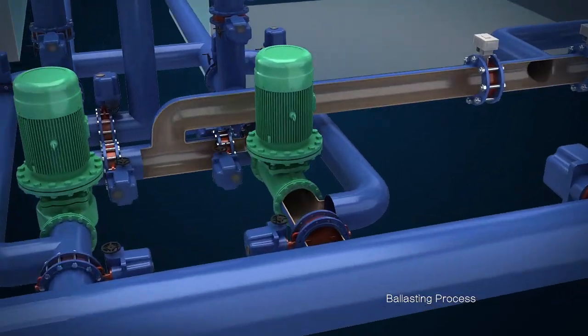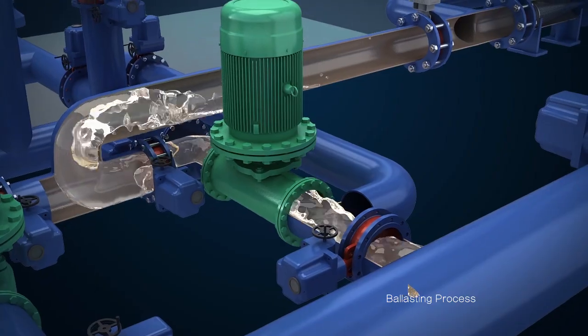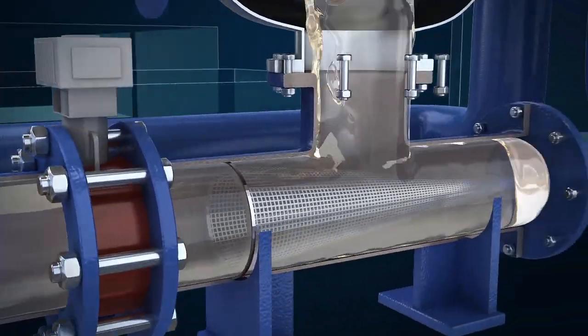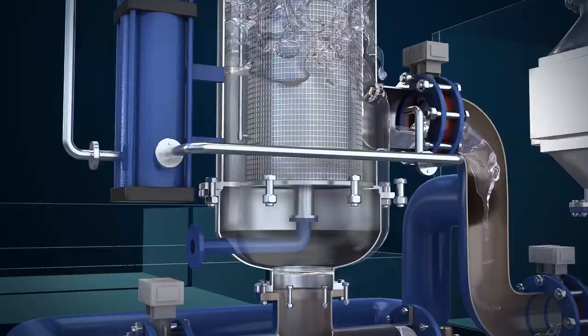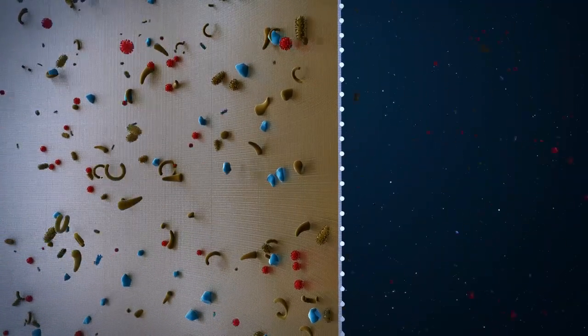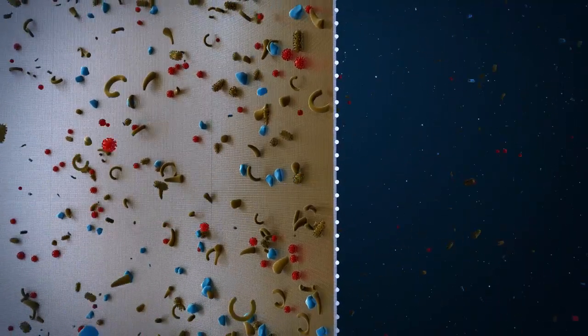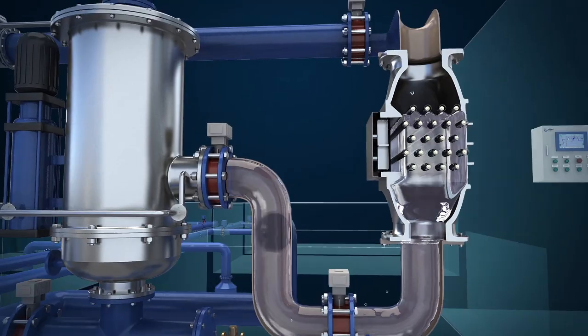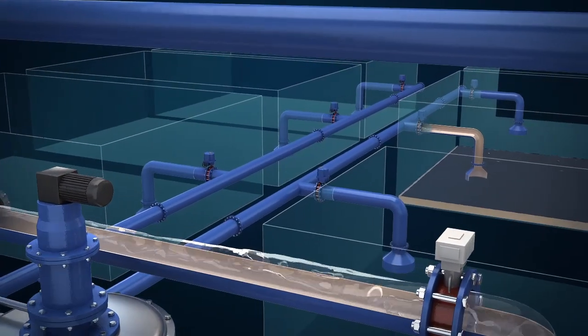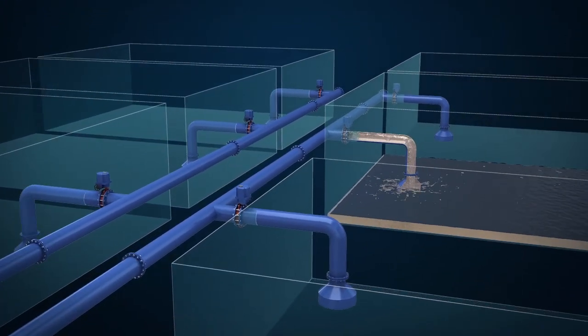Seawater enters the system by ballast pump and passes through strainer prior to entering automatic back flushing filter. Remove organisms and impurities over 20 microns in filter and then passes through EPT unit. Organisms are killed under combined effect of ultraviolet and ultrasound. Finally, seawater is pumped into the ballast tank.